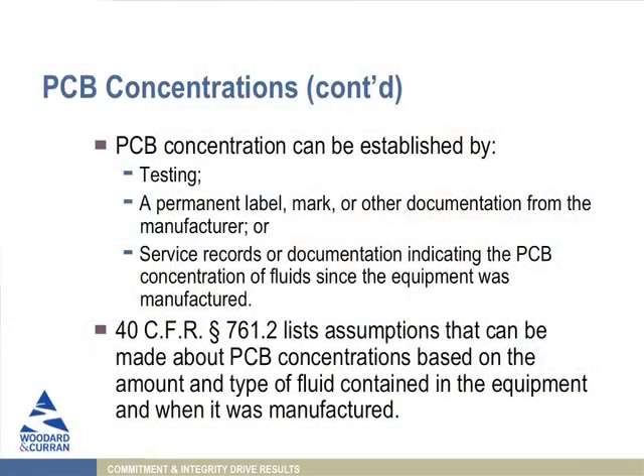There are different ways in which you can determine the concentration. You can test it. There may be a mark from the manufacturer. There may be some service records. The key thing is that there are some assumptions that the regulations require you to make. If you don't have a mark on it that says no PCBs, then if you have a date on there, that date becomes very important. The key threshold date is July 1979. Earlier than that, then you have to presume that the equipment, the transformer, had 500 parts per million PCBs.